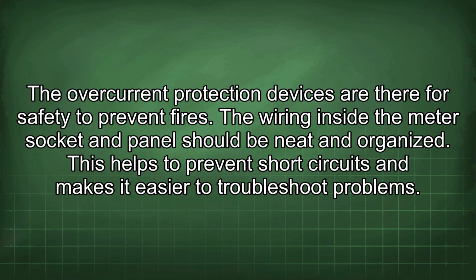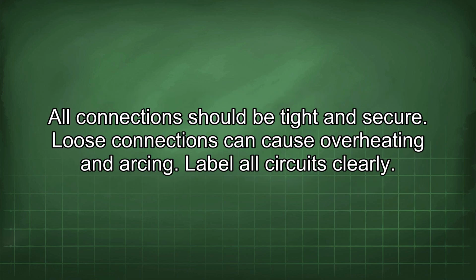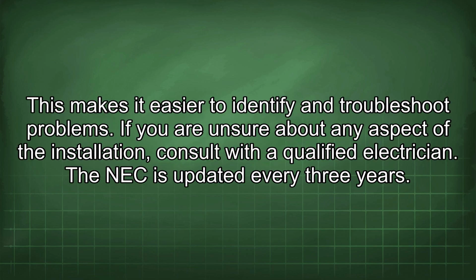The wiring inside the meter socket and panel should be neat and organized. This helps to prevent short circuits and makes it easier to troubleshoot problems. All connections should be tight and secure. Loose connections can cause overheating and arcing. Label all circuits clearly. This makes it easier to identify and troubleshoot problems.